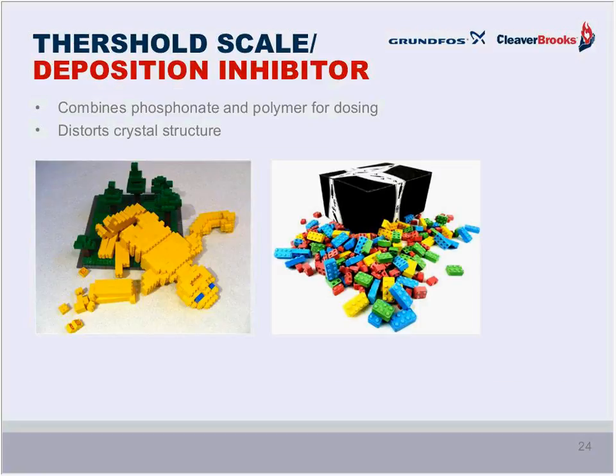Then we have the threshold scale inhibitor program, used for moderate to severe hardness, which combines both a phosphonate and a polymer together. You'll find this treatment in applications below 300 pounds operating pressure, so below that 422 degrees. As you can see in the visual, this treatment distorts the crystal formation of the calcium and magnesium, not allowing them to bind on the heating surfaces, and thereby allowing the minerals to be removed by surface blowdown.